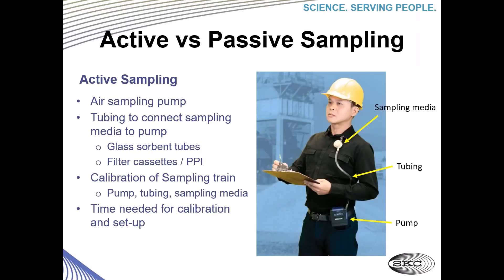Before jumping into products and applications, I want to make sure everyone understands the difference between passive and active sampling. Active sampling involves pulling air through the sampling media using an air sampling pump, tubing to connect the sampling media to the pump — whether glass sorbent tubes, filter cassettes, or in this picture a PPI parallel particle impactor — and you would also need to calibrate the sampling train by connecting the pump, tubing, and sampling media to make sure you're reaching the required flow.